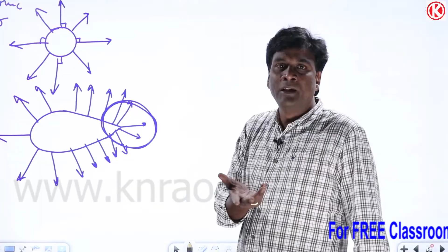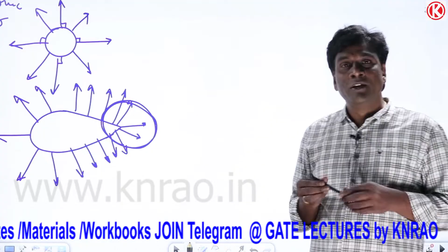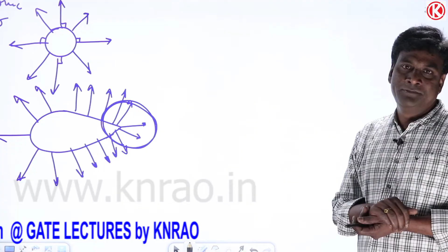We will see the formula for this later, but let me connect this with an interview question. The moment you have a sharp edge and voltage levels are more, when the voltage gradient exceeds 30 kV per centimeter maximum, or 21.2 kV per centimeter RMS value, corona will definitely occur. Can I say corona will be there only in power systems? No. Wherever you have more voltage or sharper edges, you are going to have corona.